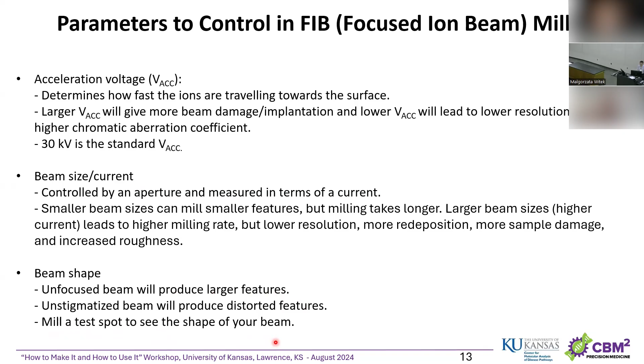So actually, in the previous slides, we need to control the voltage applied to the octupole to minimize this astigmatism of the beam. But in all, what you need to do in a real FIB is mill a test pattern using certain parameters on a blank substrate. You do the test milling, then determine the best shape and focus of your beam, and then apply those parameters for the real milling of your device.